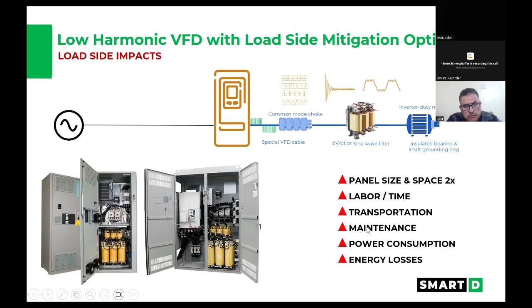So now let's talk about the SmartD solution to the line and load side. We call this the clean power VFD, and it's called that because we're able to draw a pure sine wave from the grid, and output a pure sine wave to the motor. What we've done is take the active front end idea, and instead of IGBTs, we use something called a silicon carbide MOSFET. These MOSFETs are a type of switch that switches 20 times faster than the 40-year-old IGBT technology everyone's been using in the VFD industry forever.